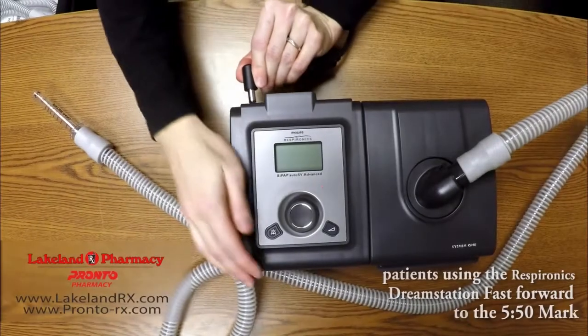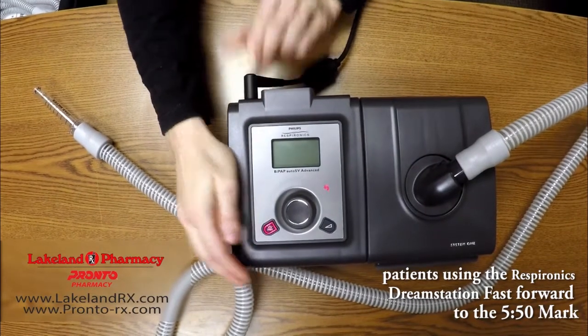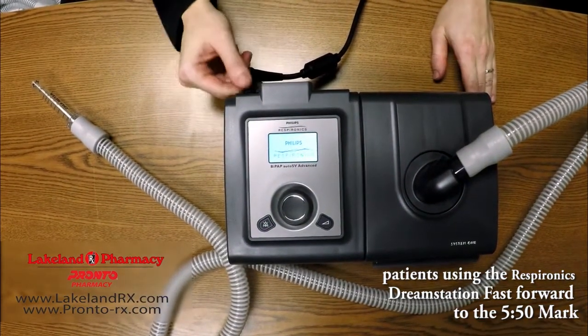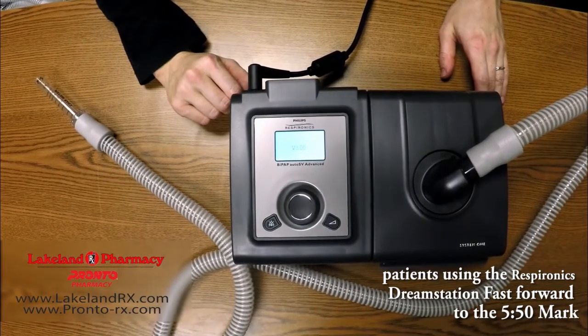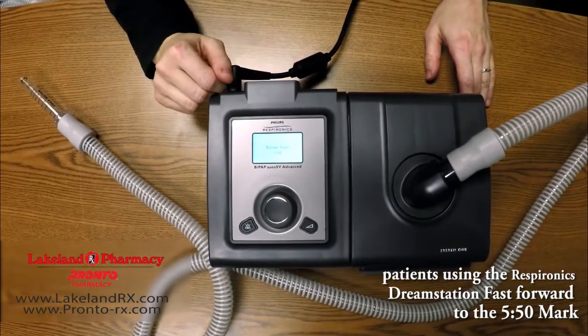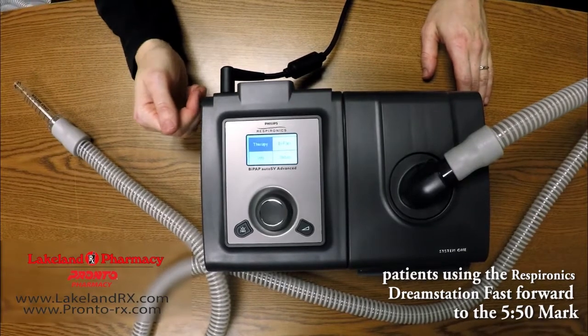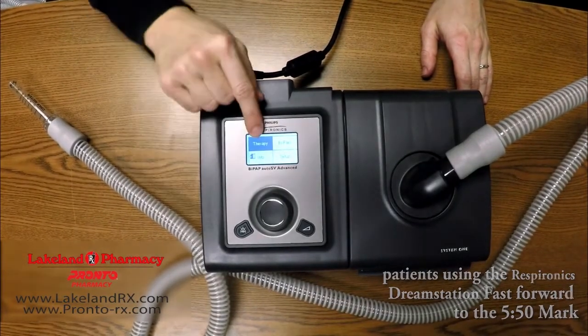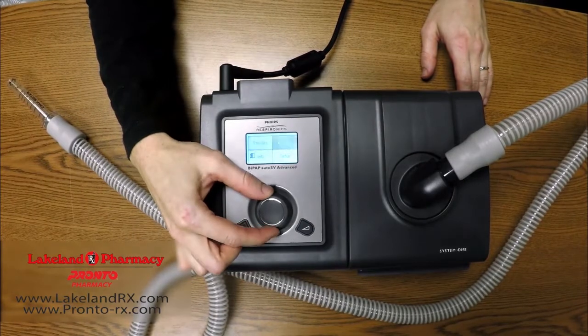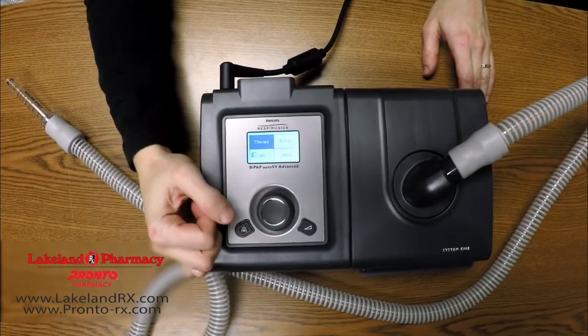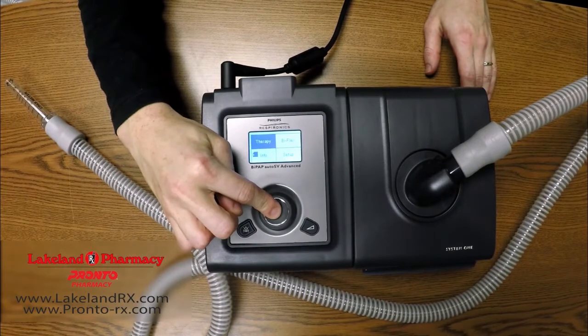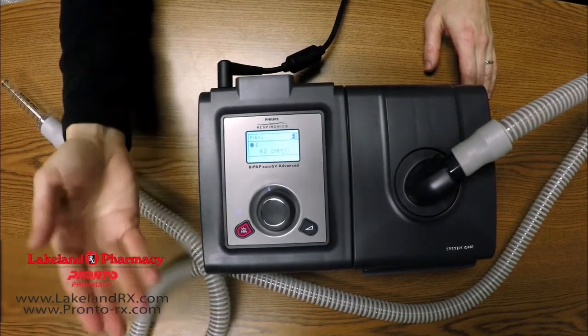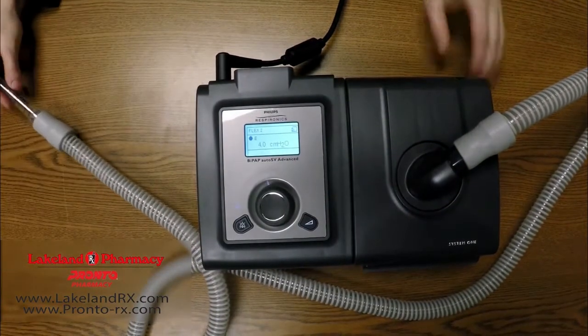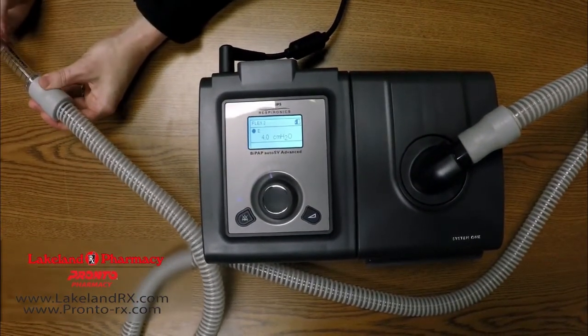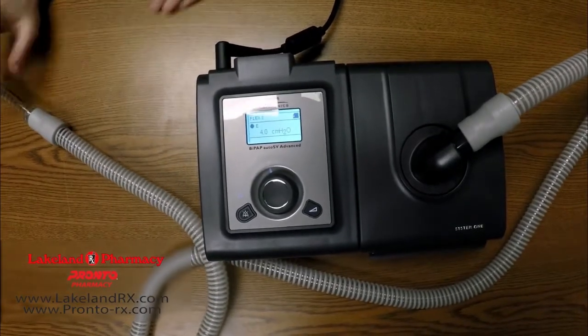Okay, I'm going to go over the machine with you to show you how to change the humidifier setting. First, all you have to do is plug in the machine, and it will show you the version, and some machines will show how many hours are on the machine. Where it shows therapy, it should be highlighted. If it's not, you just move it back until it's highlighted, and push this button down, and it will automatically start. This is when the pressure's on, you can actually hear it. You can't hear it very much right now because we have a little calibration piece on the end here.